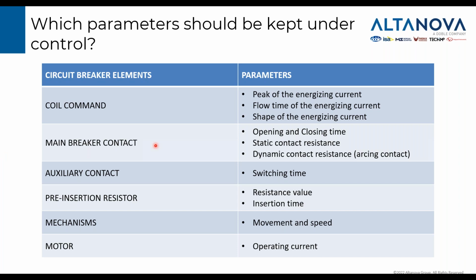For the main breaker contact, of course, we have to test the opening and closing time, but not less important, the value of the resistance when the circuit breaker is closed, and also the profile of the dynamic resistance during the operation, to understand the status of the arcing contact. For the auxiliary contacts, we have to check if they are working correctly by measuring the switching time, and when present, we have to measure the pre-insertion resistor value. The pre-insertion resistors are devices present to absorb energy during the operation.